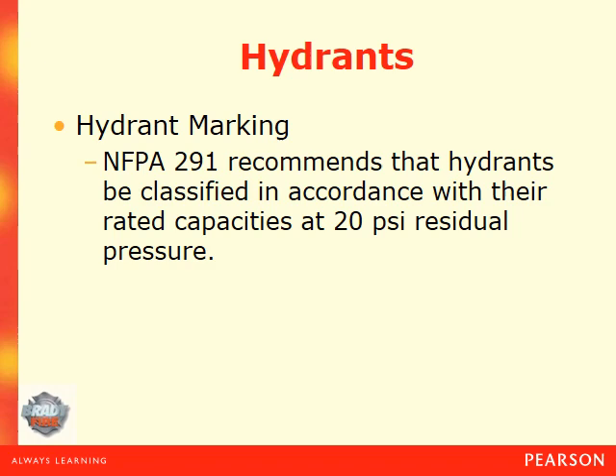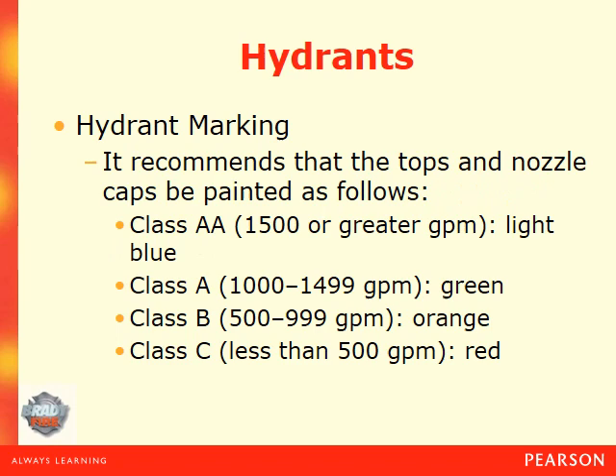NFPA 291 recommends that hydrants be classified in accordance with their rated capacity at 20 PSI residual pressure. A Class AA hydrant is capable of supplying 1,500 gallons per minute or greater and has a light blue top. A Class A green top can supply between 1,000 and 1,500 GPM. A Class B orange top supplies 500 to 999 gallons per minute. A Class C red top supplies less than 500 gallons per minute.